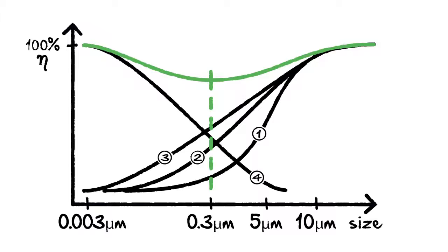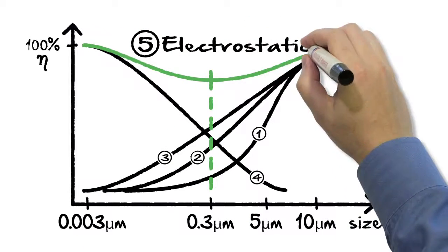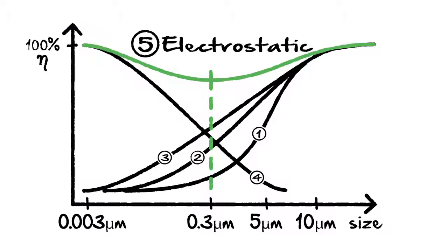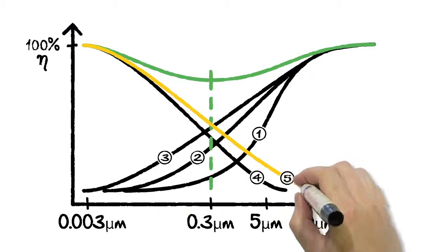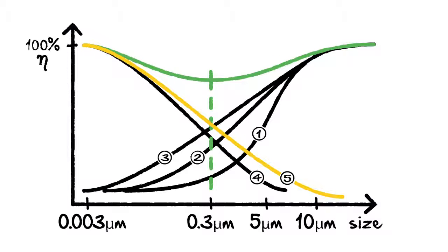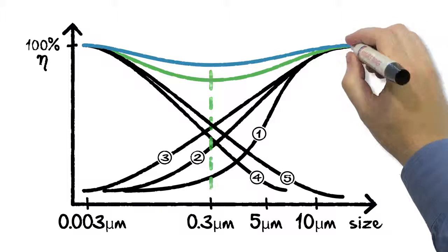What we're able to do by adding our electrostatic attraction force, the 5th force, is that it also works better for the smaller ultrafine particles, but it's not as effective when particles are really, really big. So we're adding something with high efficiency here and making a new total efficiency of the filter, where we're adding this 5th capture force. We get a filter curve looking like that.